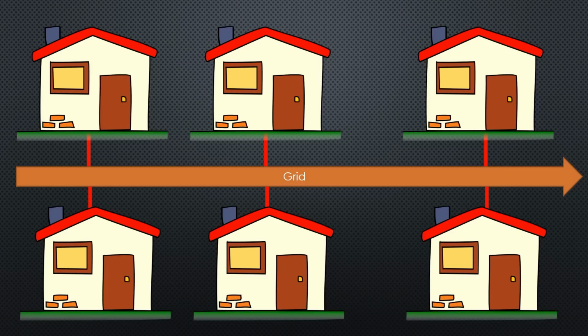So let's assume the grid no longer delivers power to our street, but our brave solar plant still produces energy. Because we are still connected to all other homes, it immediately would start to supply our whole street, maybe even others. In a fraction of a second, our inverter would overload and switch off, without the influence of Bill Gates.